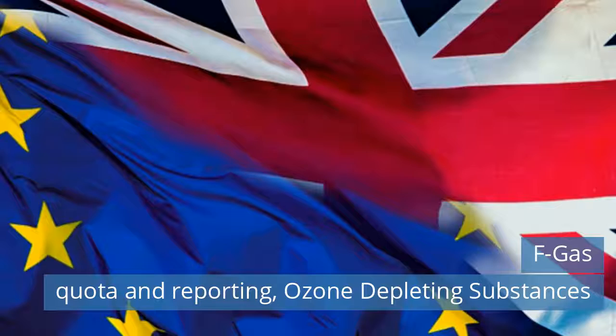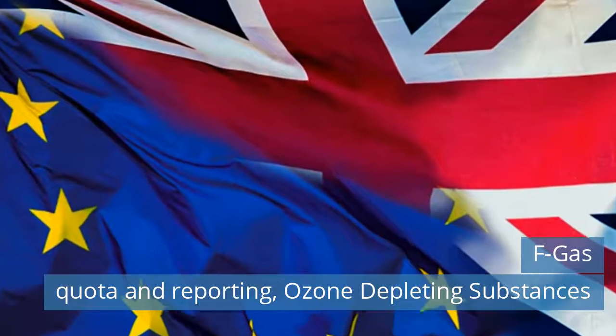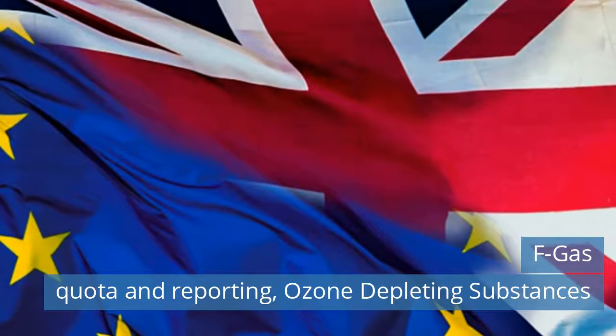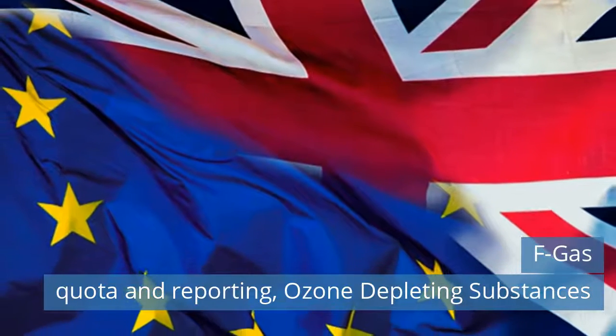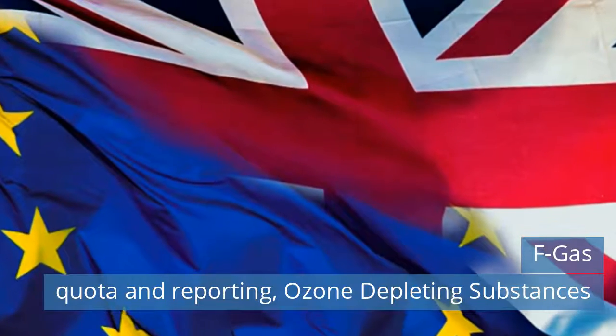From January 1, 2021, a GB HFC quota will be needed for businesses that place on the GB market HFCs equivalent to 100 tonnes or more of CO2 per year. This total includes any imports to GB from the EU or Northern Ireland. Read more of the news on our website today.